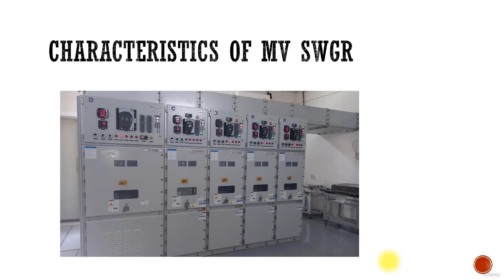So I will give you a background now on why we need a specialized terminology or specialized kind of equipment in the medium voltage levels. If you consider a switchgear, you will see this switchgear first of all is coming in a metallic enclosure. Second thing is, here in the center you can see this is the circuit breaker compartment, and the circuit breaker is installed here. Circuit breaker means a purely switching device is installed in this MV switchgear. So the control is possible through these buttons as well. So this is the emergency push button.